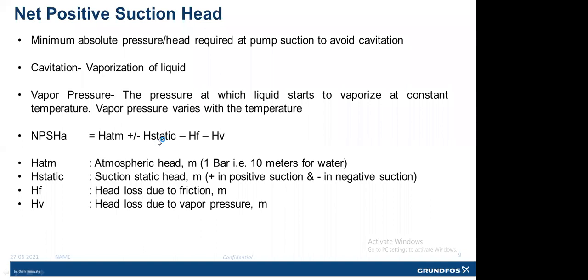If no, then we should look at whether we can reduce the frictional losses, because at most of the sites we have come across the situation where, because of lower pipeline size at the pump suction, the pump tends to cavitate. Since the pipeline size is lower, the water velocity increases, and hence the frictional losses increase and NPSH available reduces. So it is always recommended to use properly sized pipelines for the pump suction, so that the frictional losses are minimum and NPSH available at the site is maximum, and we can avoid cavitation in the pumps.